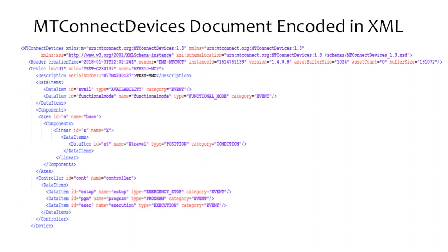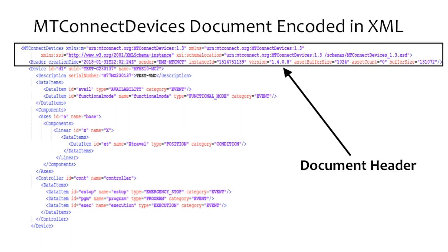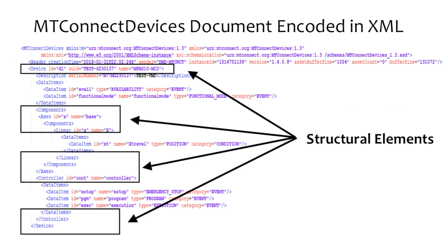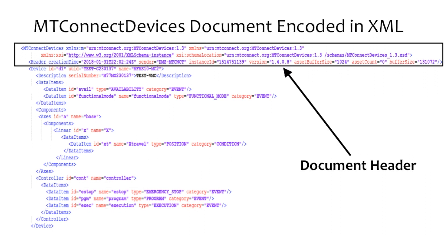Focusing on the operation and status of a piece of equipment, an MT-Connect agent responds to a request for information by publishing a response document encoded using XML. As an XML-encoded document, a response document has two primary sections: a header and a document body. The header section provides information including XML and agent version information, agent storage capacity, parameters associated with data management within the agent, and XML information required for a software application to properly decode the contents of the document.